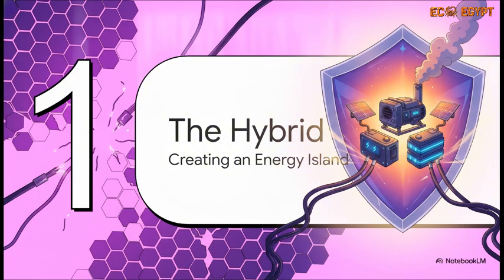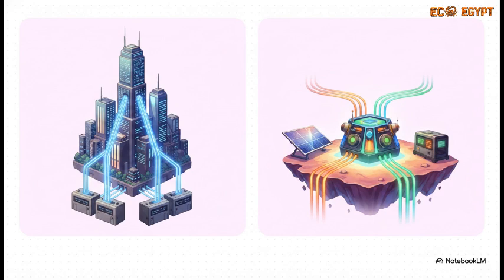Let's get started. To start things off, we have to completely shift our mindset away from standard grid-tied setups. Building an isolated energy island is just a totally different beast. Notice the stark architectural difference here. In a standard grid-connected plant, the utility grid is your master reference bus, right? Your inverters are essentially just slaves to it. But in a PV diesel hybrid, there is no grid. The system is its own isolated island, and here the hybrid controller is the absolute master. It dictates everything from breaker switching to zero export.